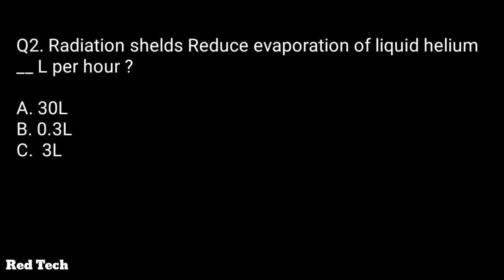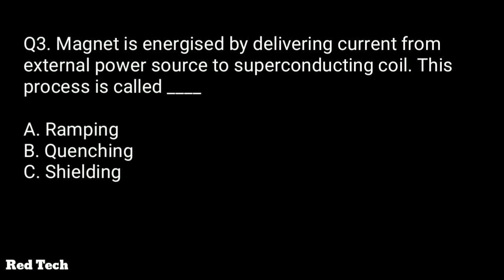Question number two: radiation shields reduce evaporation of liquid — how many liters per hour? The options are 30 liters, 0.3 liters, and 3 liters. The right answer is 0.3 liter per hour, which basically reduces the evaporation of helium gas.